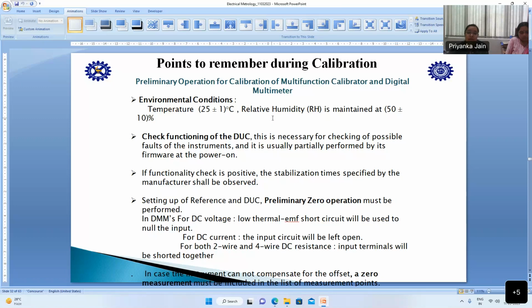So in case it is not under preliminary zero operation, we need to make them zero. And we need to cross check whether the thermal EMF short circuit has been taken care of or not. Most of the time when you are doing calibration using a DMM, we have to short the ends and do the thermal EMF short circuiting to avoid the offset which comes into the picture.